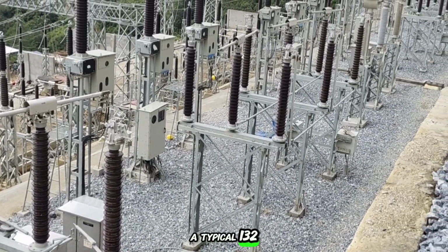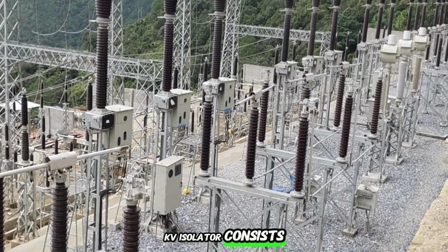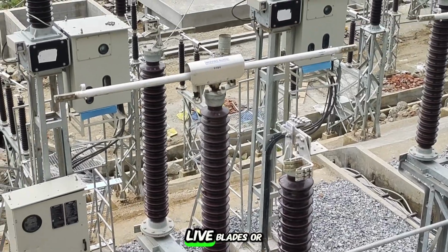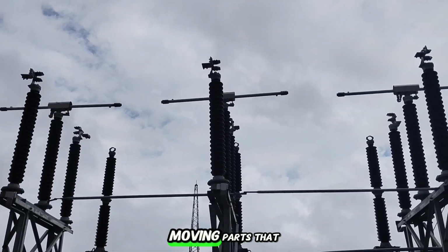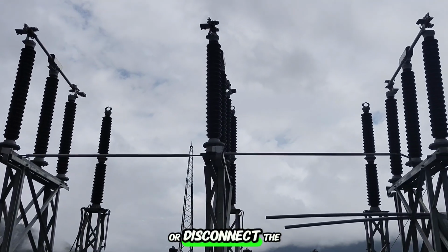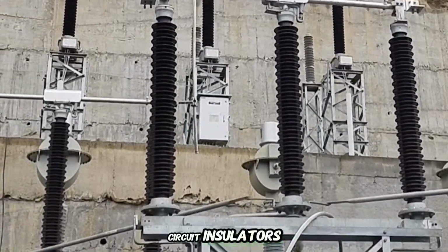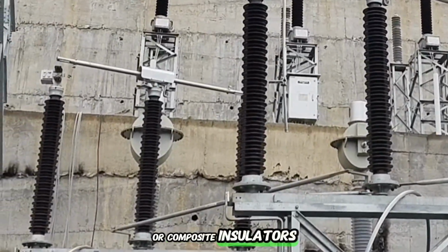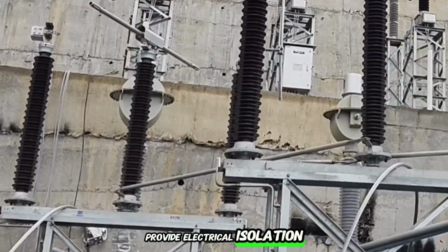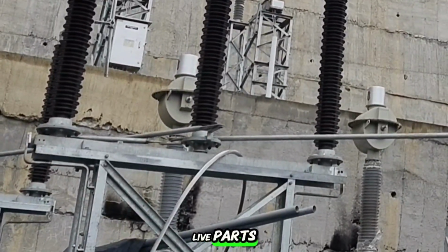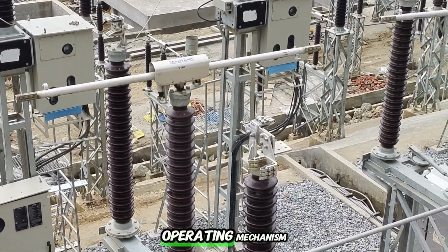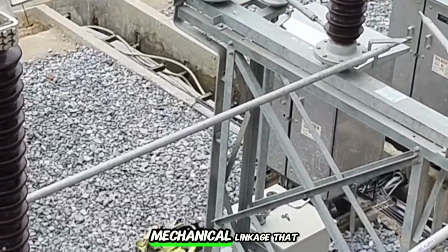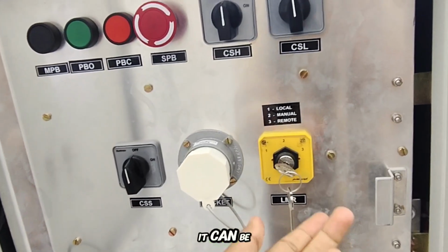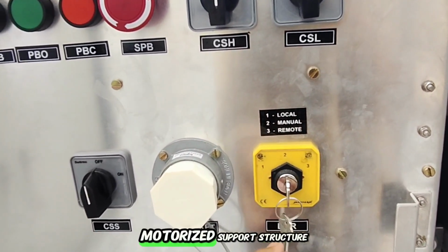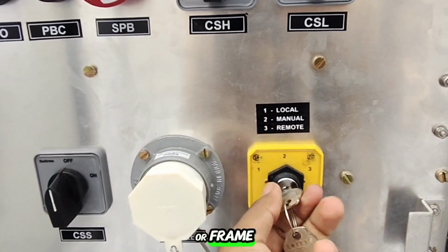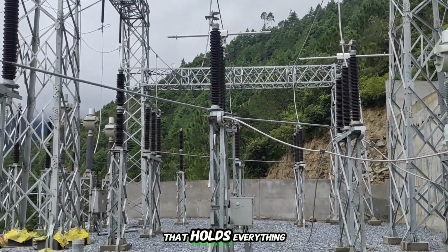A typical 132 kV isolator consists of several key parts. Live blades or contacts. These are the moving parts that physically connect or disconnect the circuit. Insulators. The tall ceramic or composite insulators provide electrical isolation from ground and support the live parts. These are vital at high voltage. Operating mechanism. This is the mechanical linkage that moves the blades. It can be manual, lever operated, or motorized. Support structure or frame: the robust frame that holds everything together.